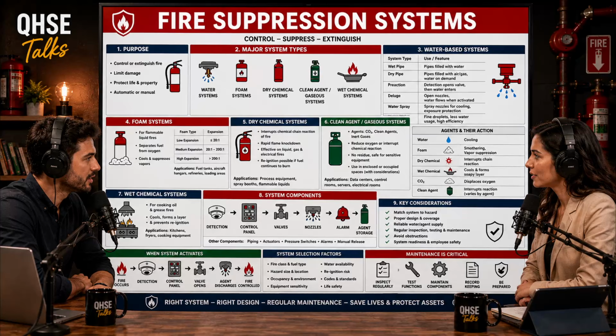Okay, let's break down the four primary types of sprinkler piping systems: wet pipe, dry pipe, preaction, and deluge. Let's start with the baseline, the wet pipe system. The wet pipe system is the simplest and most reliable. The piping network is completely filled with water under pressure at all times, right up to the closed sprinkler heads. So delivery is instantaneous. Yes. When a fire breaks out, the bulb shatters, and water discharges immediately.